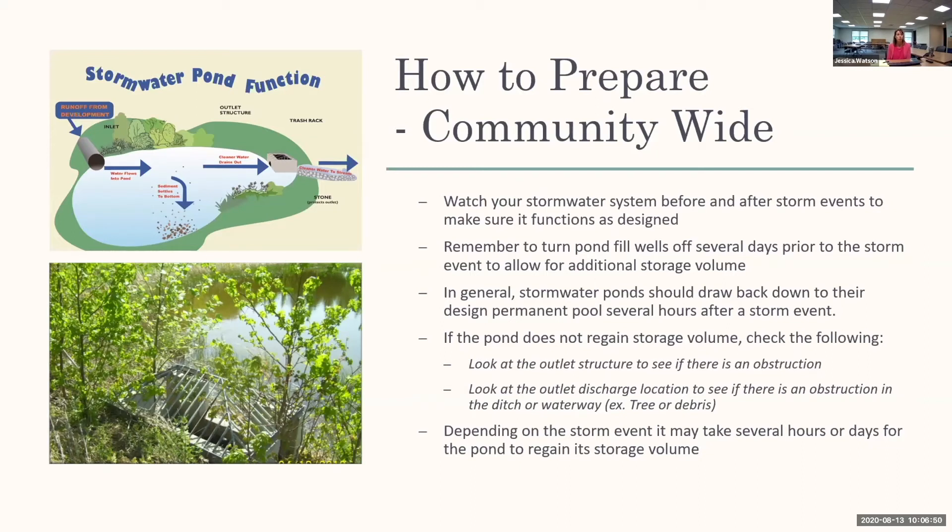In general, stormwater ponds should draw back down to their design permanent pool several hours after a storm event. Depending on how your facility is designed, it may be a couple of hours or a couple of days — it really depends on the size of the storm event. For a 100-year storm, which is 9.2 inches of rain in 24 hours, it may take up to three days for that pond to draw back down. If the pond does not regain storage volume, look at the outlet structure for obstruction — trash, woody debris — and also look at the outlet discharge location, such as a fallen tree root system or debris blocking drainage. Depending on the storm event, it may take several hours to days for that pond to draw back down.